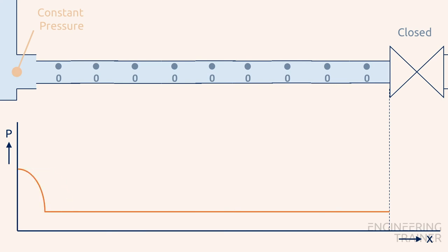Once the pressure wave reaches the constant pressure boundary condition, resulting from the infinitely large reservoir, the same thing happens as before. The pressure gradient cannot continue and the situation in the pipe shows now a lower pressure in the pipe than the pressure of the boundary condition. Because of this pressure difference between reservoir and pipe, water will start flowing into the pipe.